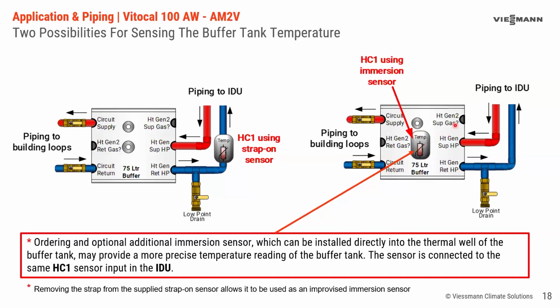Now, the upside of this is that when there's no flow in this piping to the indoor unit, and you have flow here for the system while the system is making, let's say, domestic hot water, this sensor will know the temperature of this tank. It will know it's deviating from the set point. So when it switches back from domestic hot water, it will already know how far away from the set point it is, as opposed to over on this side, where we had to wait for the flow and then it would see that temperature drop or rise, however we're going to look at it for cooling or heating. So in my opinion, this is a more accurate way to do it. Putting the sensor in the tank allows the control to see what's going on in the tank in real time all the time, and it will make it a little bit more accurate, in my opinion.